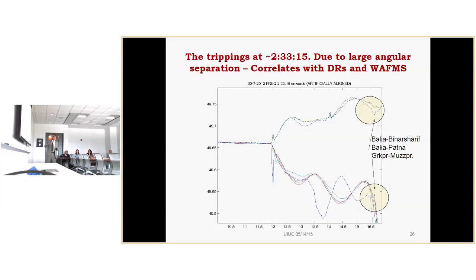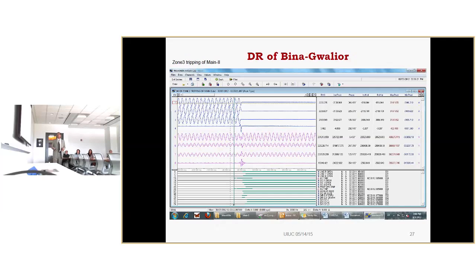For the PMU plots, wherever you see the sudden variation, it is either generator tripping or throw off of the load. This is the time when western separated from northern, and this is the time when eastern region got separated from the northern region, and northern region was under blackout for almost 14 hours. So 350 million people, trains were stopped. A lot of inconvenience to the people.